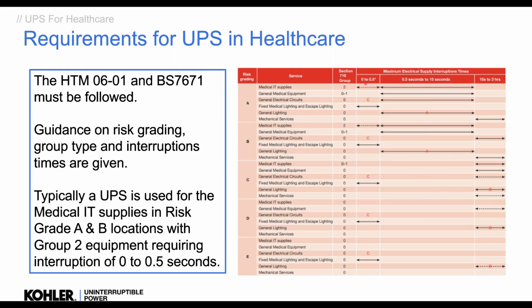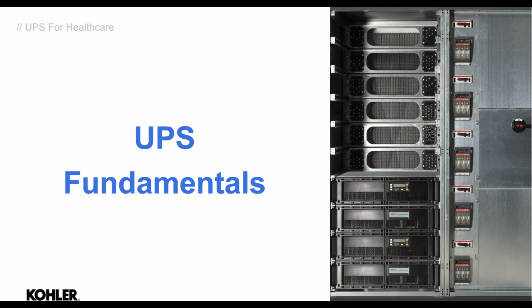So this is typically where we're going to have it in medical IT sections for risk gradings A and B. So this is where we're going to typically have that UPS application. But there are lots of other applications where we have UPSs for lighting and for admin and everything else in the healthcare sector. But we're going to be typically looking where we need to back up the medical theatres and recovery areas, etc., like that.